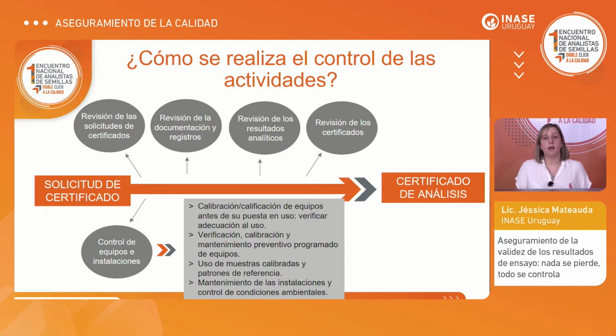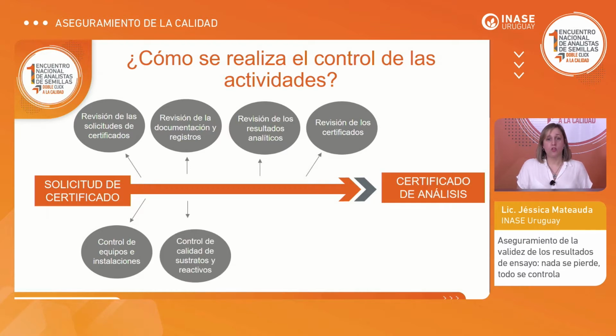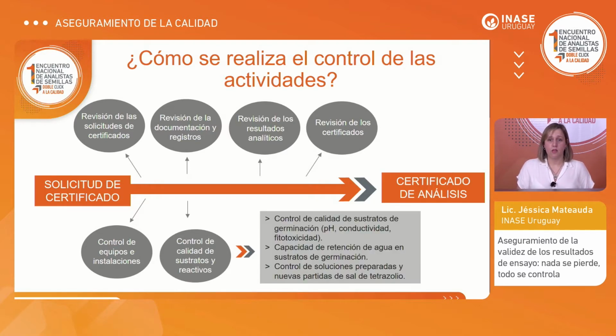To use calibrated samples and also reference patterns. That's very important. We have to use them in every case to check scales. We have to use calibrated weights, for instance. For thermometers, we have to have some reference thermometers. And something very important, we must not forget the facilities and the environmental conditions. It is critical to have control over that, and it's very important the place where we store the samples, to keep certain conditions, so that if I have to repeat a test, it's possible to reproduce it.